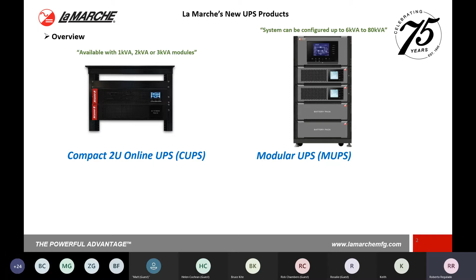Some of the basic characteristics or specifications of the compact UPS is going to be obviously rack mountable, but as far as power, they're typically going to be a 120, 230 volt input output, single phase only, so single phase in, single phase out. And the actual voltage ratings on the battery side are going to depend on which module you select. So for example, the 1 kVA is going to be available at 24, the 2K at 48, and the 3K at 72 volts DC.